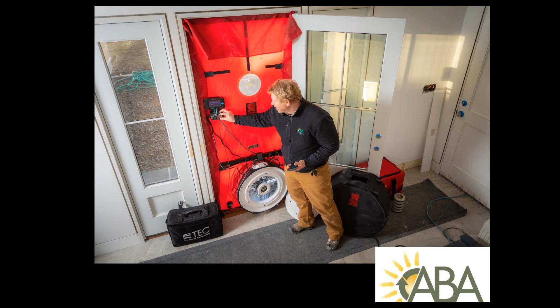Next slide. This is a building air tightness test report for this project. Look at the CFM airflow. It's remarkable, it's around 200 CFM. These guys said they had a 450 CFM kitchen exhaust hood. So in other words, they were pulling more than twice the air out of the building than our blower door needed to bring it to negative 50 pascals. Negative 50 pascals is like a 25-mile-an-hour wind blowing on the building, or a little bit more. So when they turn on that kitchen exhaust hood, it's like a 50, maybe 60-mile-an-hour wind blowing from every direction. That's the amount of pressure they were putting that building under with just that kitchen hood.